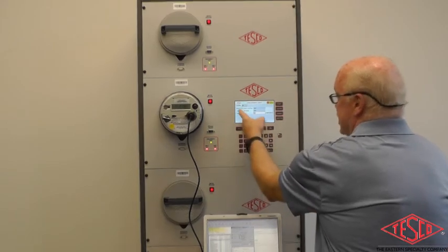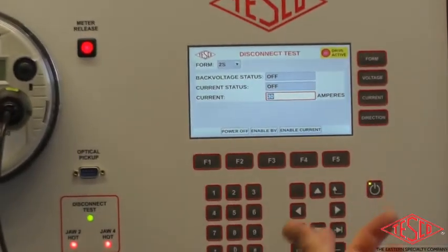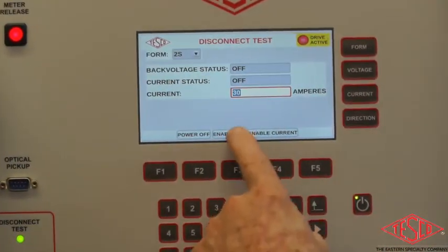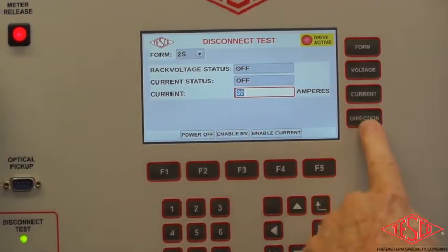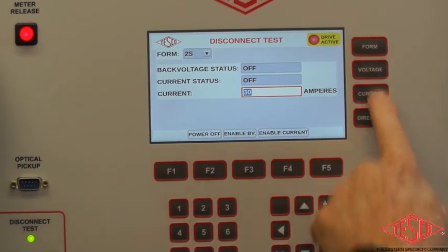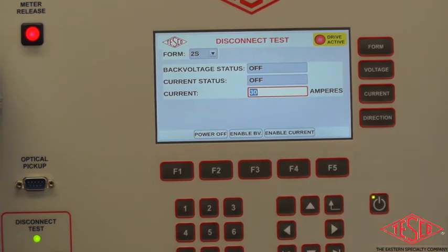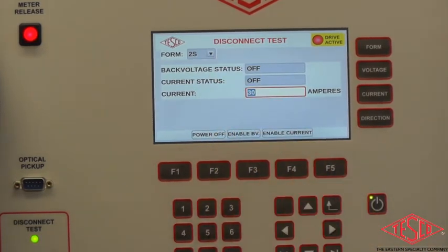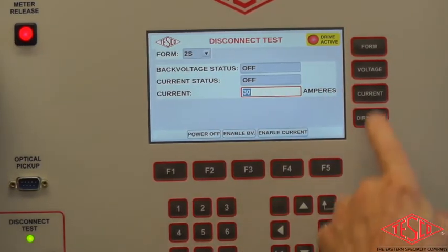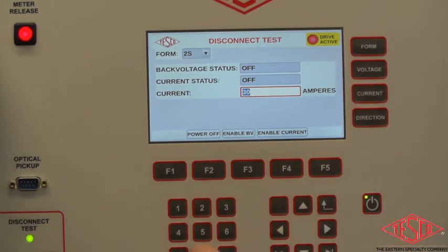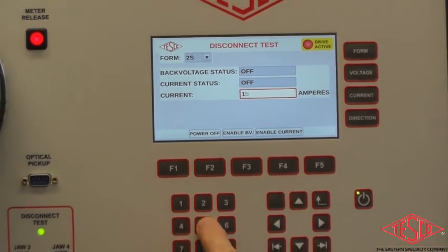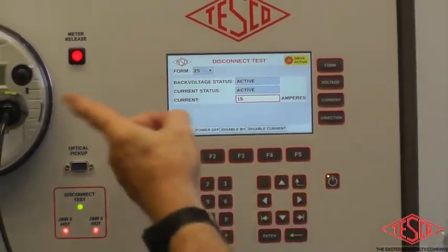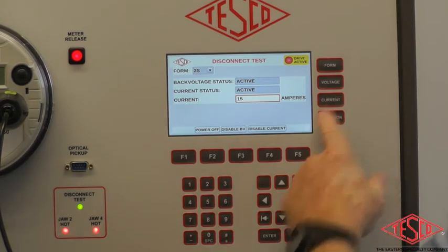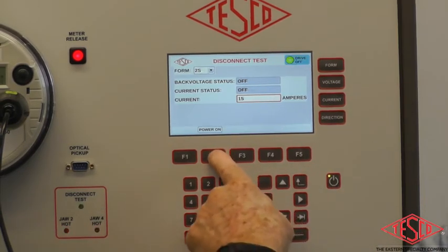Maybe there's something I haven't shown you: you can change current. If you want to do 30 amps or you can do 50 amps, you can just type it in. These functions over here are also highlighted. They will highlight a certain feature on the main screen and on this screen. So if I want to do current, I just press this one. And then if I want to do 15, press 15. Now when I enable current, it'll be 15 amps on this meter.